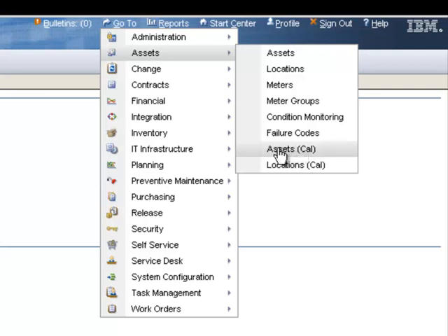I've seen some sites where they do not use any of the standard applications. They only use the calibration applications. They're basically just another mask into the same data tables within Maximo. So they do that to reduce the amount of applications that require validation. That's especially important for regulated industries. What you'll find if you use all the assets applications is there are a few more features in each one and a few more fields that just would not apply to, say, a standard pump or a motor. So their logic is I can reduce my number of applications being validated and used, and if you're pulling up a record that is not calibrated, those fields just don't apply and you leave them blank.